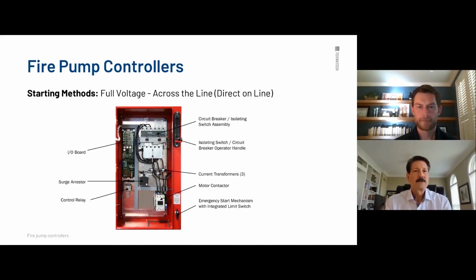People ask, where's the tipping point? Well, you might be looking at a 75 horsepower, 480 volt motor. For all I know, typically you could use it across the line with no problem, but it's the application you need to look at. What will be affected in the facility that this is going to start into? When you get into 100 horsepower, 125 at 480 volt or bigger, it seems that it's a no-brainer that you are going to use a reduced voltage controller.